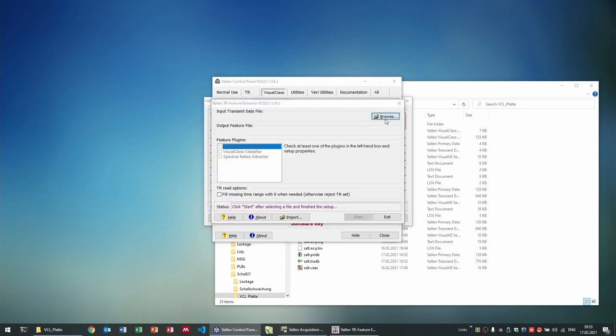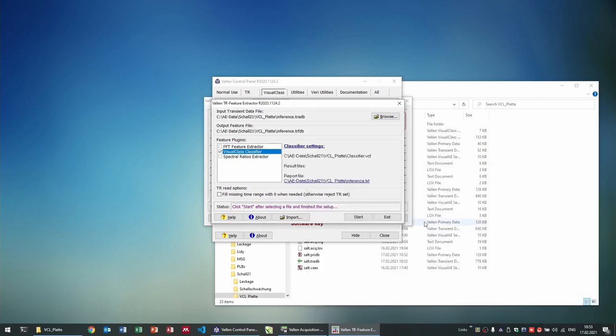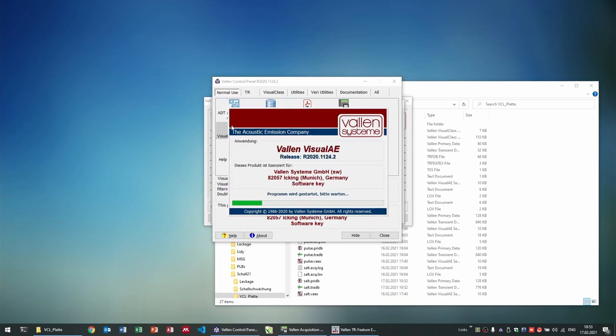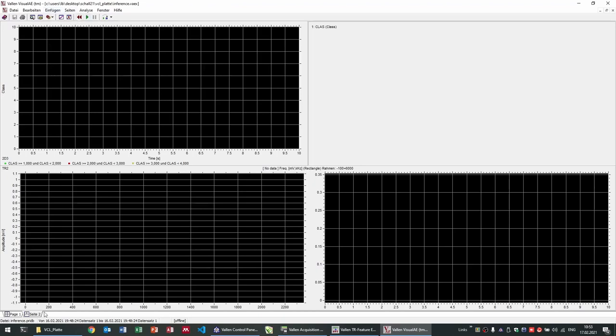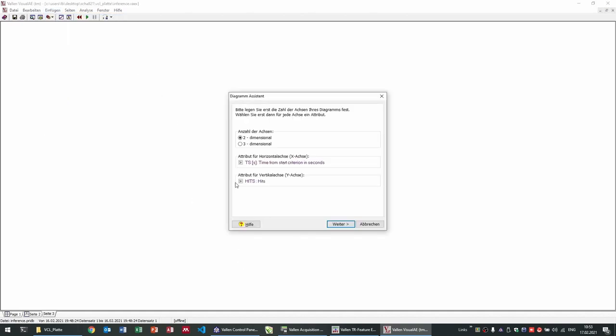Finally, it will be demonstrated how the model can be incorporated for classification during live measurements. To do this, we set a new measurement. In addition to the current acquisition, the feature extractor is also started, which receives a link to both the current measurement file as well as the exported classification model. As soon as a new dataset or hit is recorded, the features are extracted, selected, transformed, and the classification result is calculated.